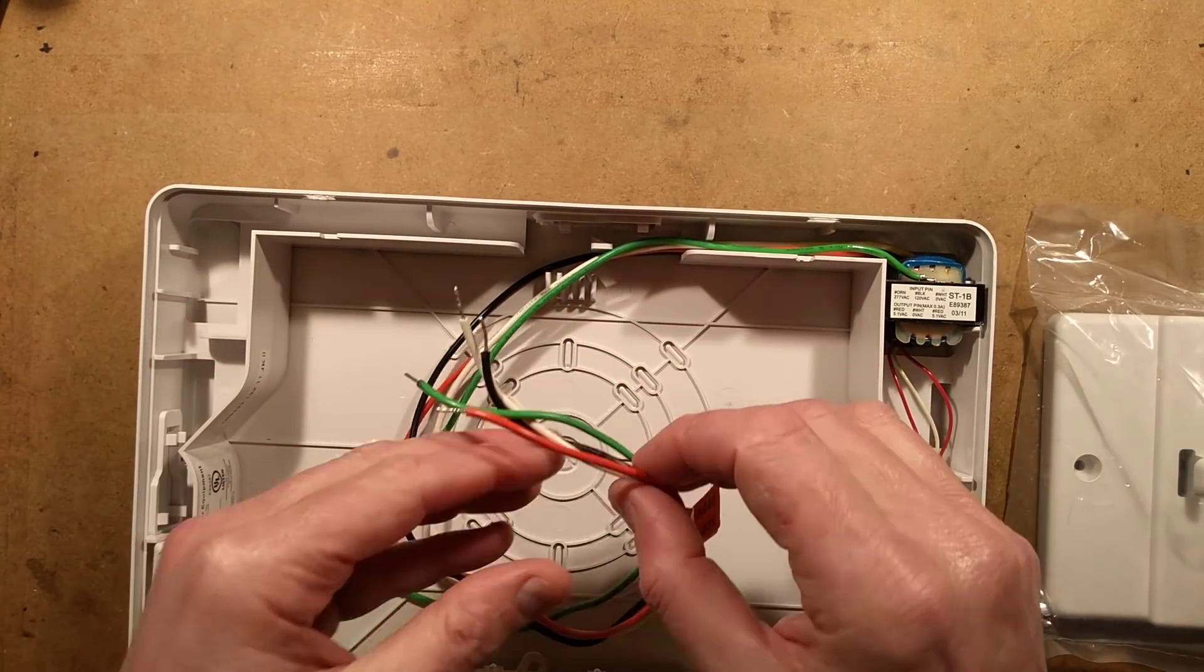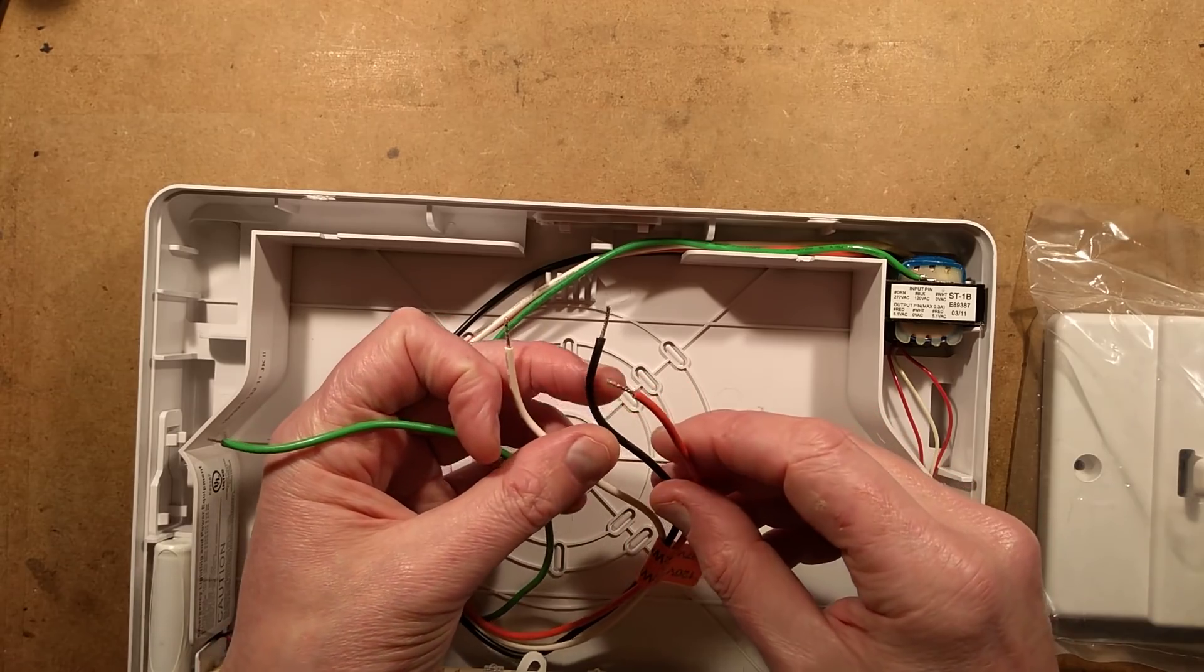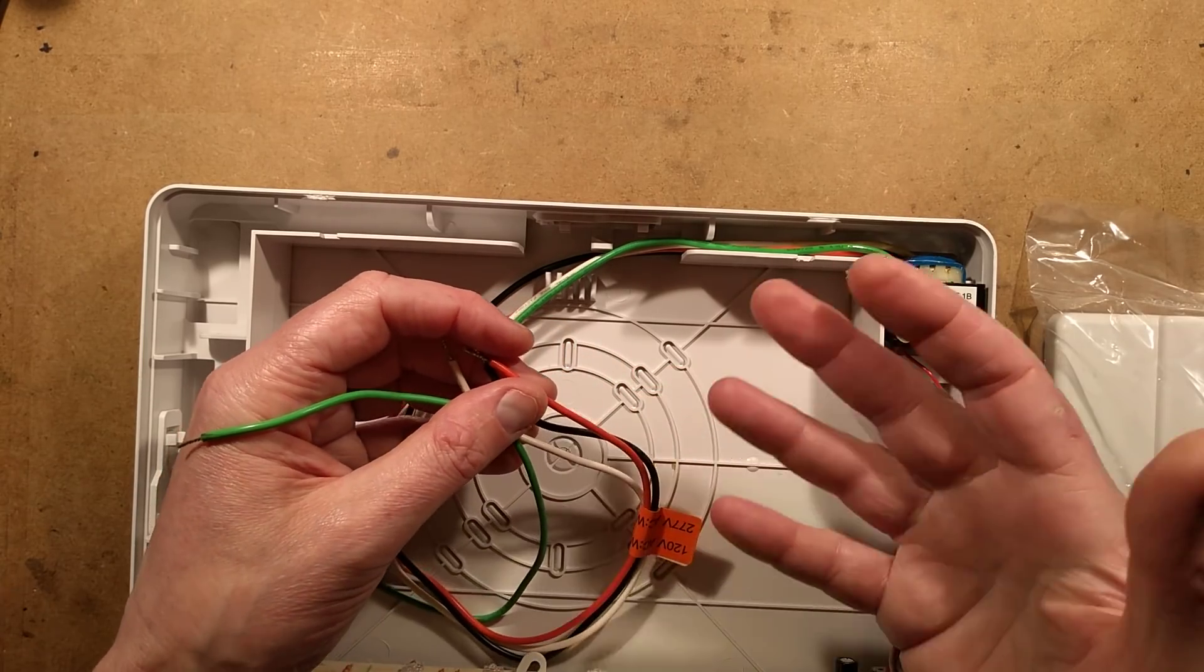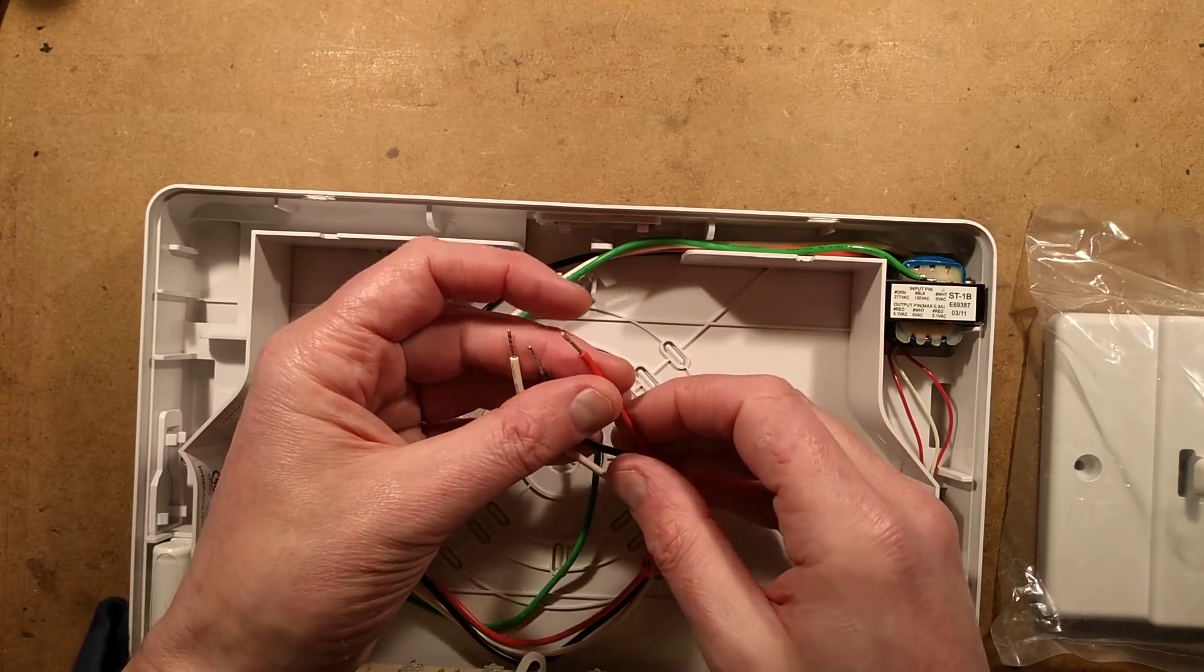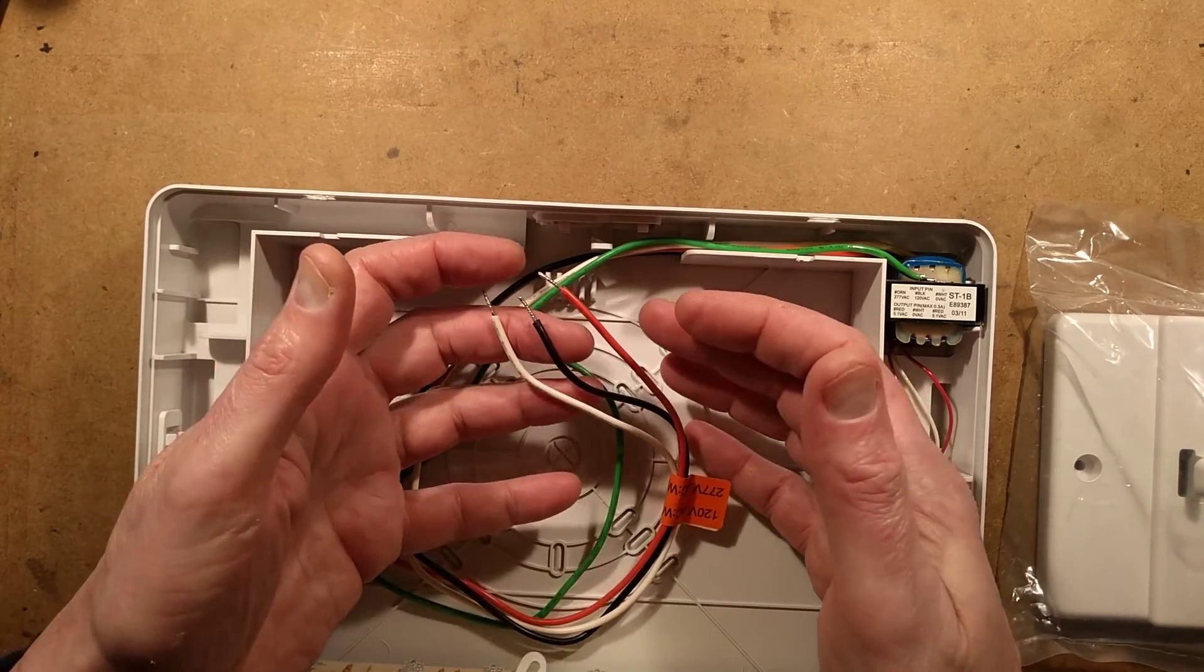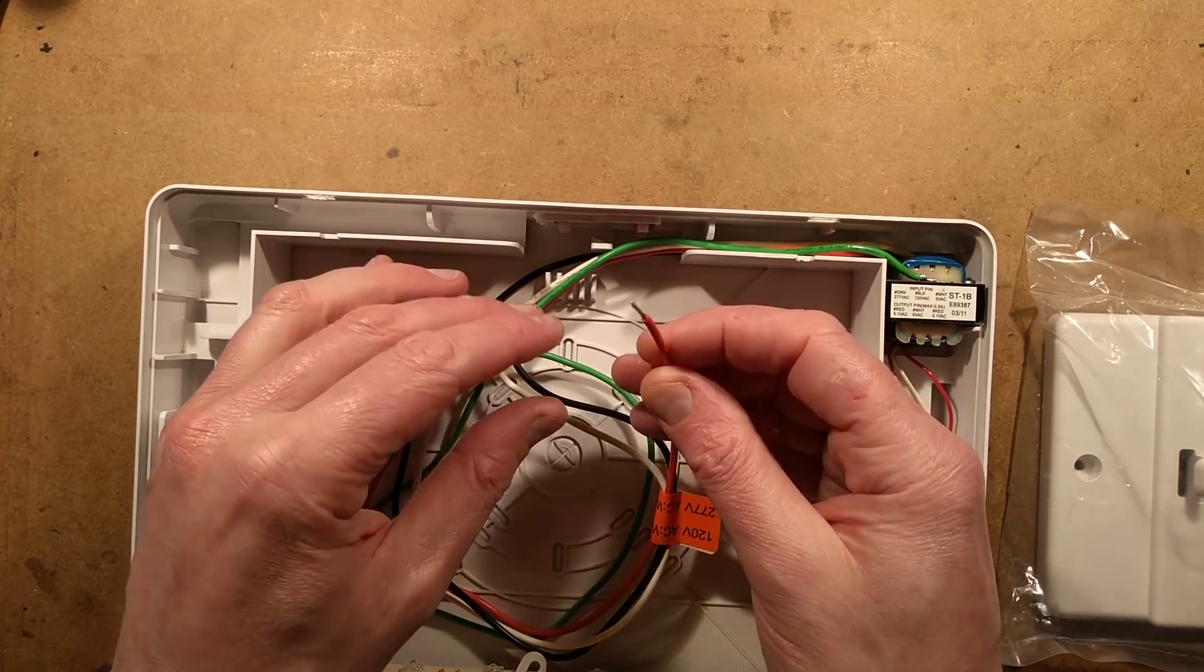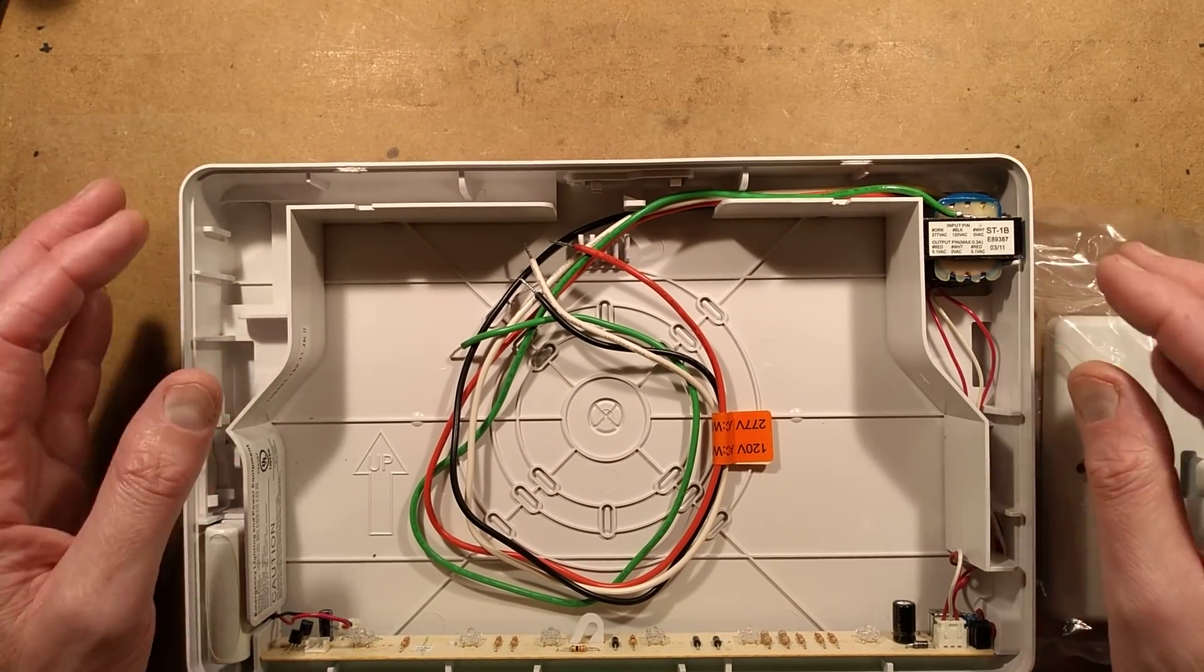The white is the common or neutral, black is 120 volts, and red is 277 volts. In America they have multiple voltages for different applications. While most houses have 220-240 volt supplies, in industry and commercial applications they have 277 volt supply for lighting because it's better suited for things like ballasts.